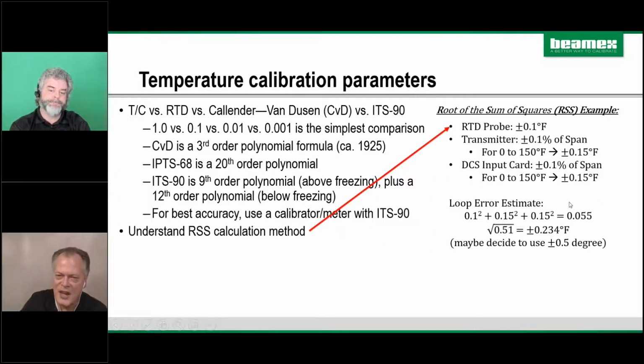So okay, here's the RSS calculation. You square each component, you get this crazy number. Oh, and I didn't update the slide. You take the square root of 0.55 and you will get what I call a statistical average of 0.234. So it's not as bad as the 0.4, but it's not as good as any of these single elements in the loop. So now this is sort of math, right? It's kind of crazy, but I'm going to say maybe we should say we're within 0.5 degree. So that's what we used on our test today.